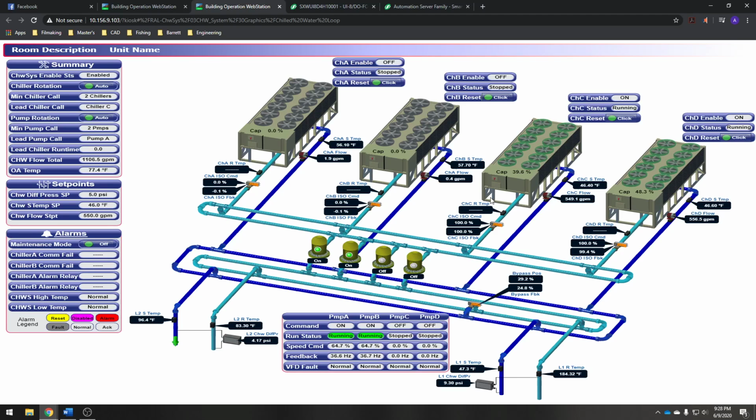That is the chiller's only job, to supply 46 degree water. As we talked about, it's the isolation valve's job to make sure this chiller is enabled and water is flowing through the unit. It's the pump's job to maintain this differential pressure. It's the bypass valve's job to maintain minimum chiller flow. So everything has one job. As long as it works, everything works perfectly, and the data center is nice and cool.